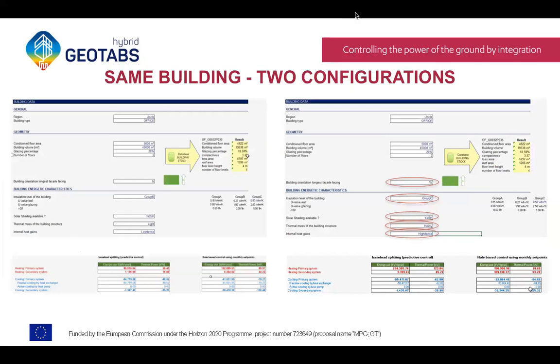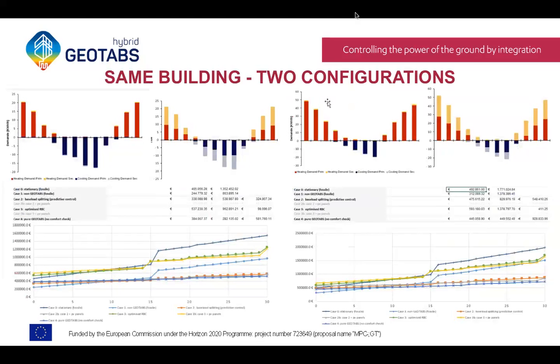In terms of predictive control and monthly set points, on the left I still have scenario 1, and on the right the second scenario. With my choice of input parameters on the left, the bore field balance due to total heating and cooling demand is approximately balanced, also for the monthly set points. But for the second case, the heating demand is much higher than the cooling demand, so there's an unbalance. By playing with the monthly set points, as shown in the graph on the right, I can improve the bore field balance, even though the predictive control indicates an unbalance.